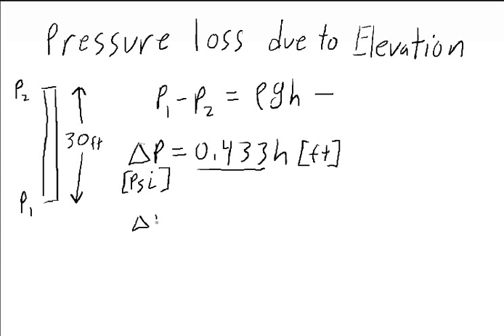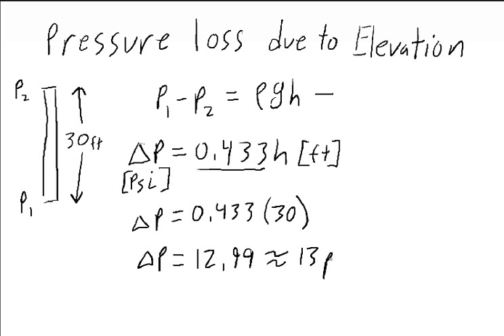So we'll have delta P is equal to 0.433 times 30, which is equal to 12.99, which is nominally equal to 13 psi.